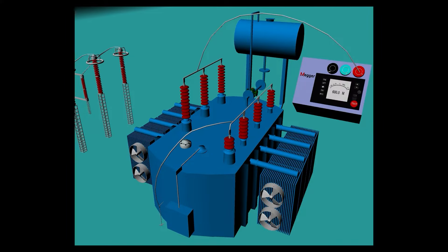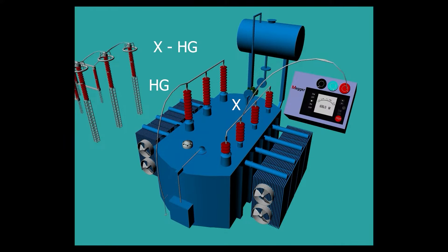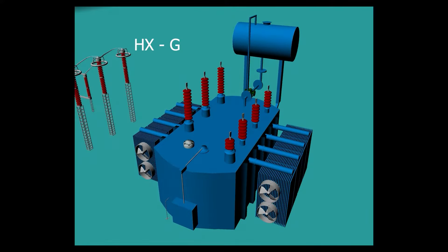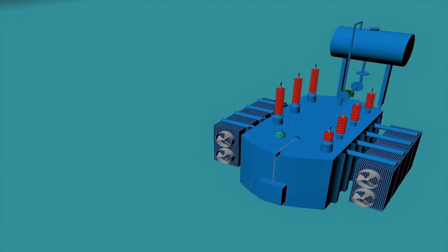We connect one lead of the mega set to the HV windings and another lead to the LV windings and ground combined. Similarly, HX-G means we connect HV and LV windings together as a single point, then connect one lead of the megger set to this single point and another lead to ground.